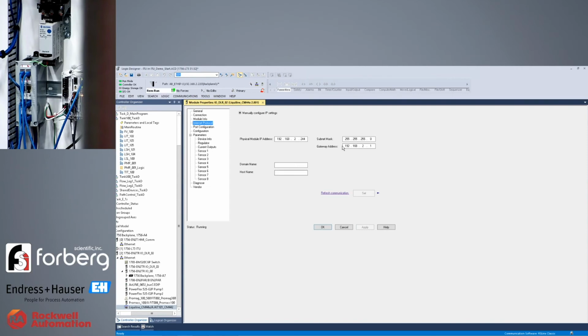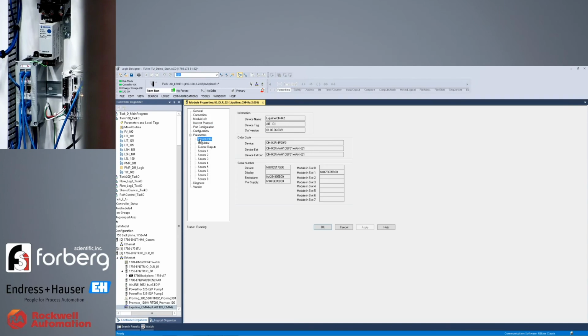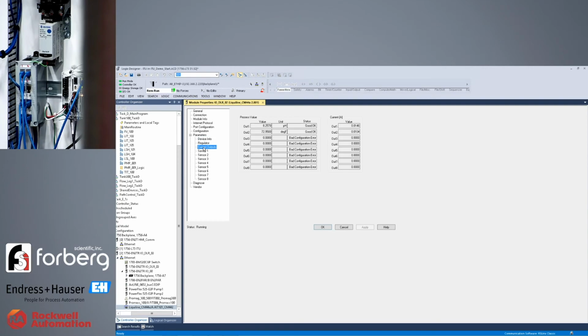As I step into the Device Info tab, you'll see that it shows a lot of the details around the configuration, the serial numbers of the devices, and the corresponding Memosens, analytical probes that are plugged into this specific Liquiline analytical device. Next, as I step down to the current outputs, I see the device is configured to provide both pH and temperature. And as I look at that tab, both of those values are showing up with a status good or okay. So you know that it's actually reading the probe and it's giving us live values back from it.